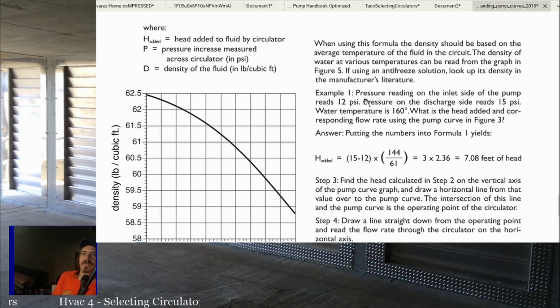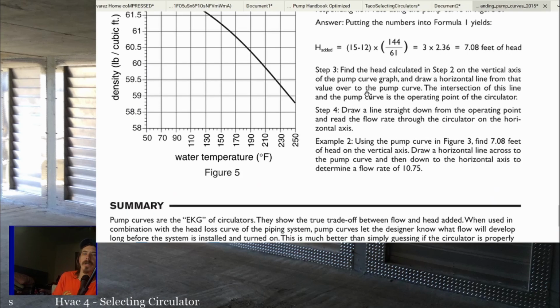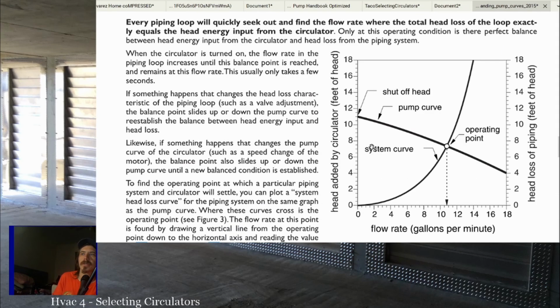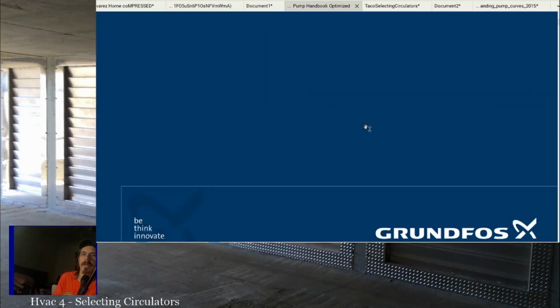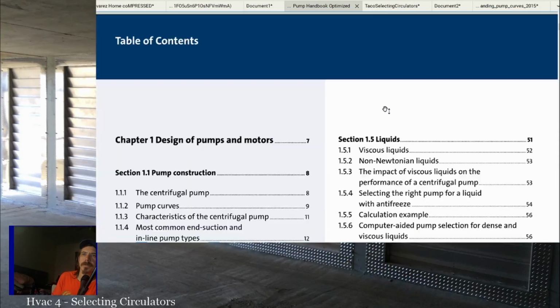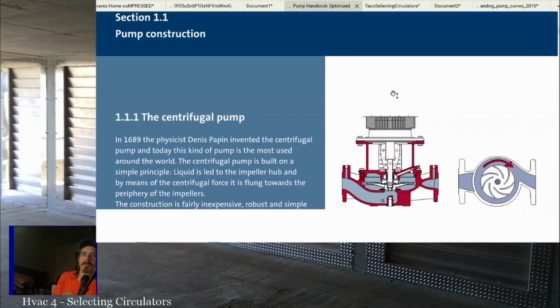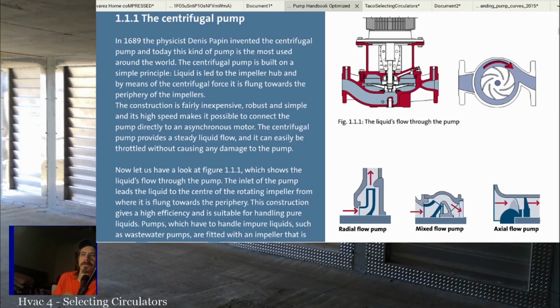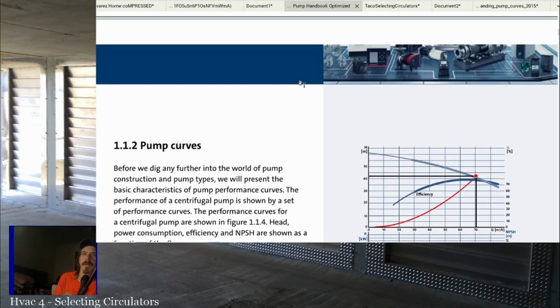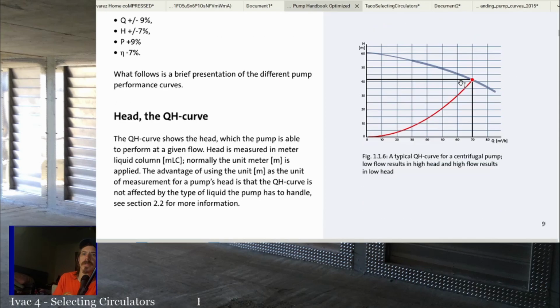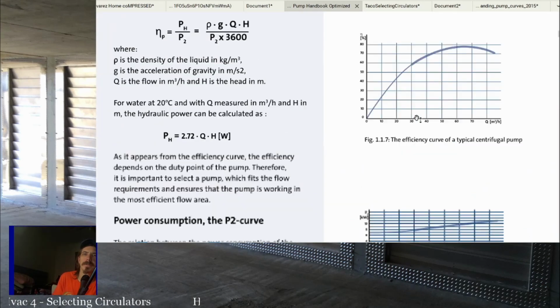And then do they go over efficiency curves? No. The other thing you'll have in here sometimes is your actual efficiency curve. So it'll tell you where the pump's most efficient. And in the Grundfos book, it shows you that. So a lot of times pump curves will have an actual head curve and then an efficiency curve, and what's the other ones? This is the Grundfos one. See if I can find this real quick. Dang it. Come on. Got the pump curve, you got an efficiency curve, and then you'll have the head curve. So it's part of the pump curve basically.